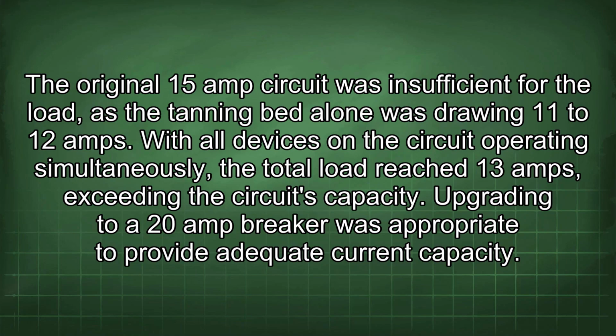The original 15 amp circuit was insufficient for the load, as the tanning bed alone was drawing 11 to 12 amps. With all devices in the circuit operating simultaneously, the total load reached 13 amps, exceeding the circuit's capacity. Upgrading to a 20 amp breaker was appropriate to provide adequate current capacity.